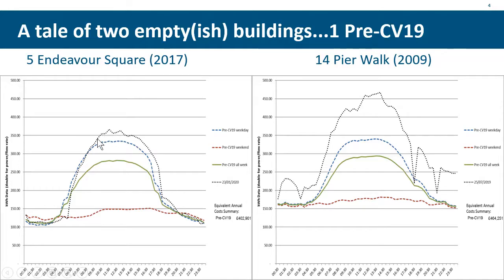What you notice from Endeavour Square is that the peak doesn't rise much more than the average, whereas in 14 Pier Walk it's much higher, because on your summer day, 25th of July, all those electric chillers are kicking in at 200 kilowatts a time, and it really chops and changes everything. And we've got a bunch of pumps as well that have to run at night because we've got a serious water circulation problem.